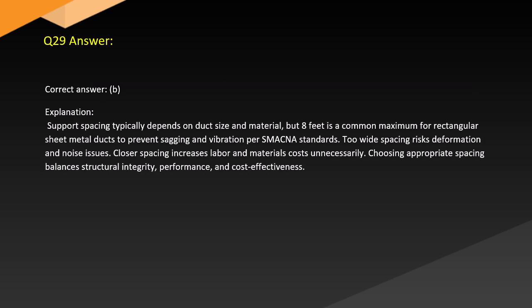Answer. Correct answer: B. Explanation. Support spacing typically depends on duct size and material, but 8 feet is a common maximum for rectangular sheet metal ducts to prevent sagging and vibration per SMACNA standards. Too wide spacing risks deformation and noise issues. Closer spacing increases labor and materials costs unnecessarily. Choosing appropriate spacing balances structural integrity, performance, and cost effectiveness.